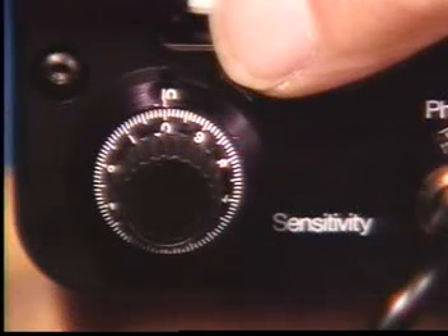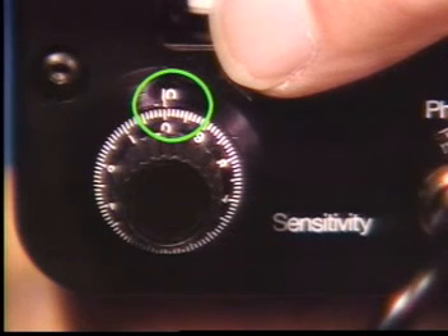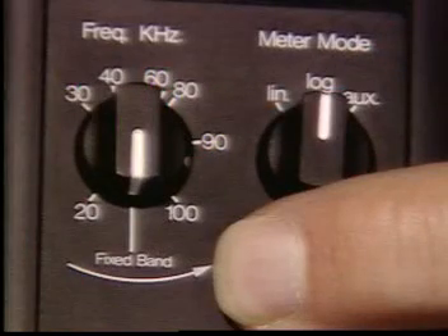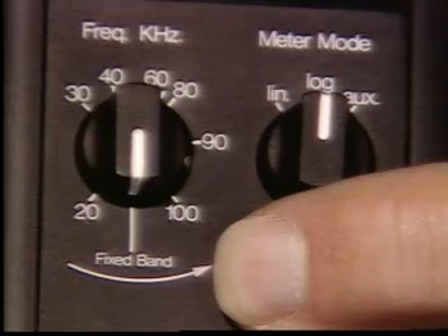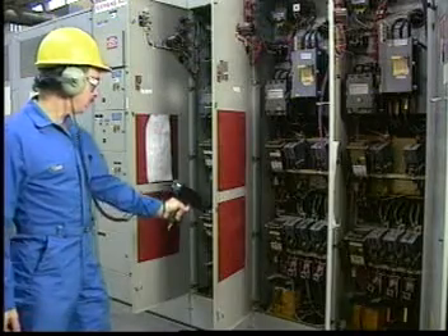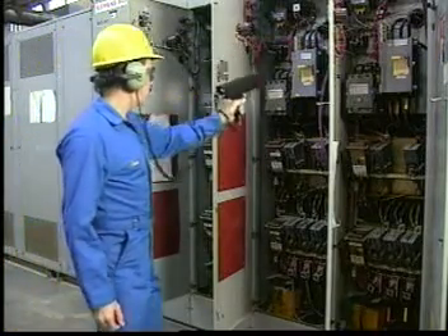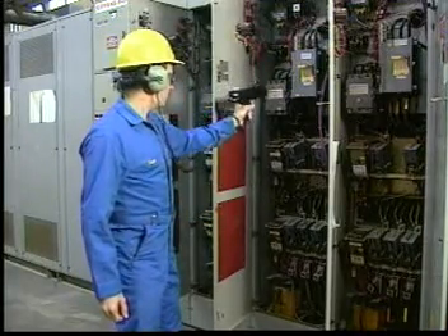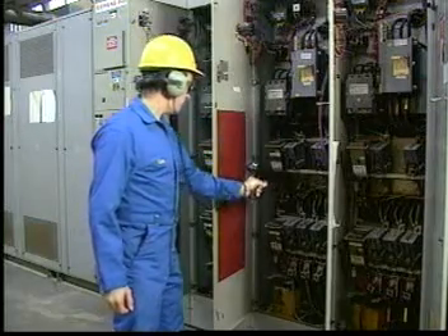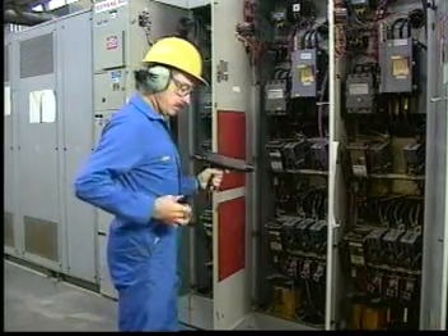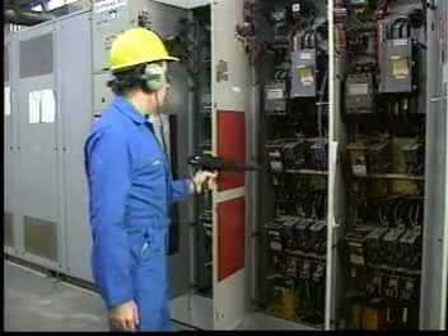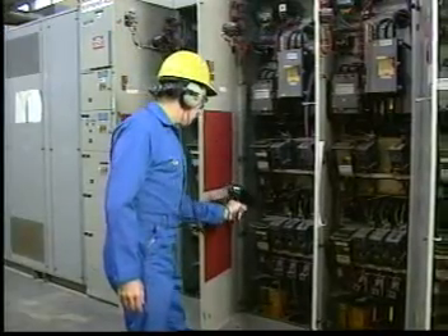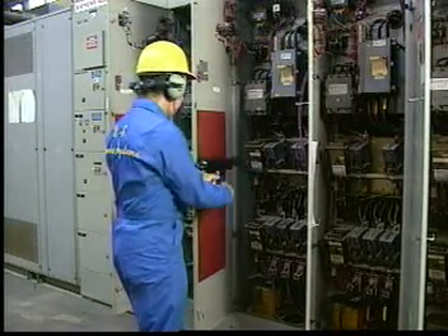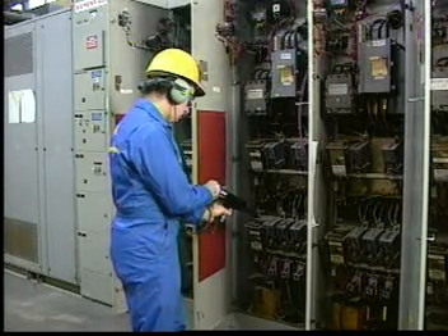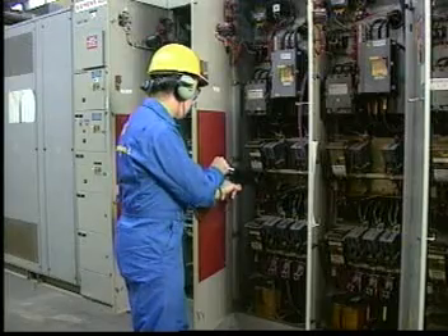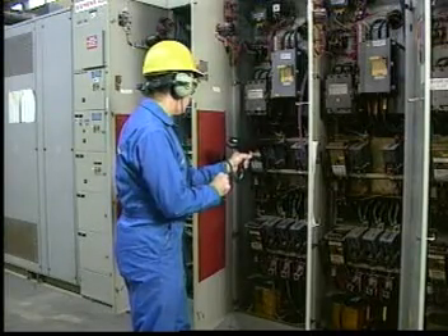To pick up gross signals, scan with the sensitivity level set for most situations at maximum, or 10. Use the fixed band mode. The meter mode should be in the log position. Scan the area, closing in on the leak site by listening for its characteristic buzzing or frying sound. Next, use the rubber probe to narrow the field to get closer to the leak site. But always respect the power of electricity. Don't get too close. Then reduce the sensitivity to pick up the fine ultrasonic signals and listen.